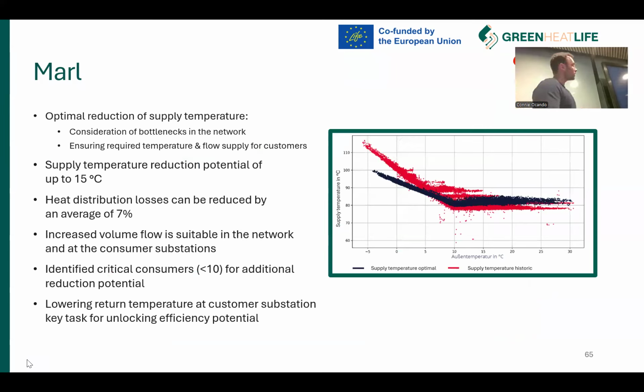You can see some results here from supply temperature reduction. First of all, for this optimization we stick to two main points. First, the network, the pipes, should handle the increased mass flows. As you know, when supply temperature reduces, we increase the volume flows, so the network needs to handle that. Second, the supplied customer should always get enough heat supply, from a flow point of view, but also from a temperature point of view. Keeping these points in mind, the digital twin showed us that we can decrease the temperature very much.